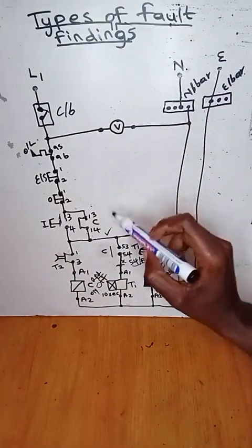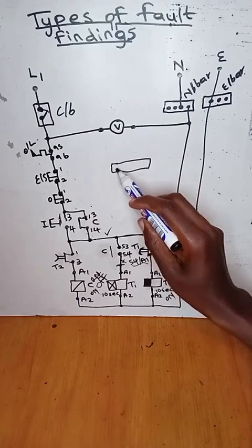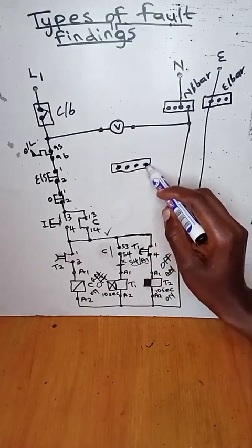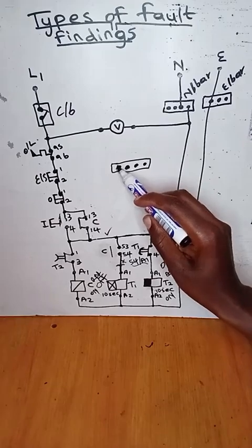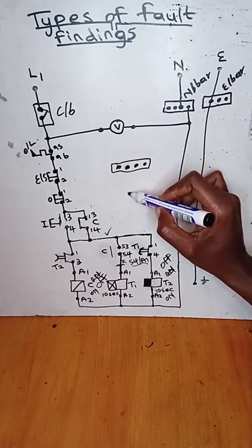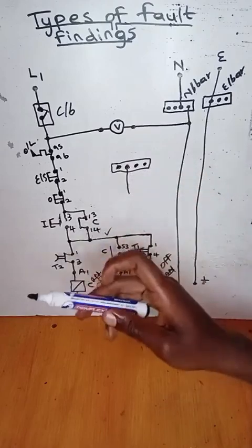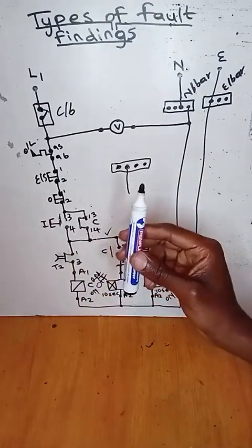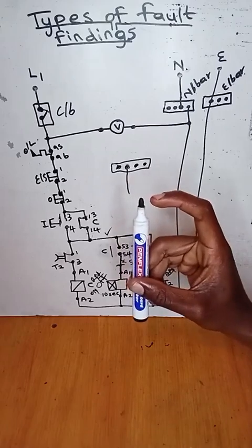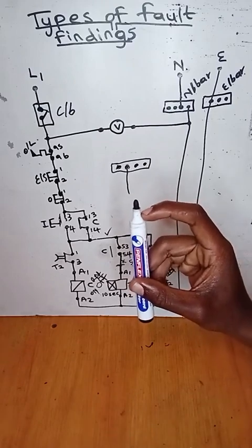Another thing that you must be careful with is when you connect your wire, maybe in your neutral bar or your E bar or your circuit breaker, you must make sure that your wire is connected correctly to the right point, and the bolt is connected to the copper of the wire, but not the insulation of the wire, right?